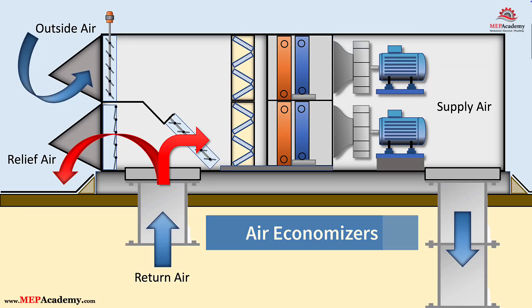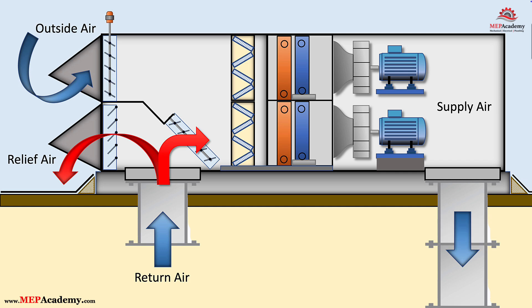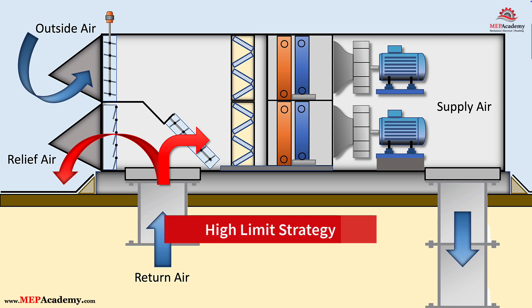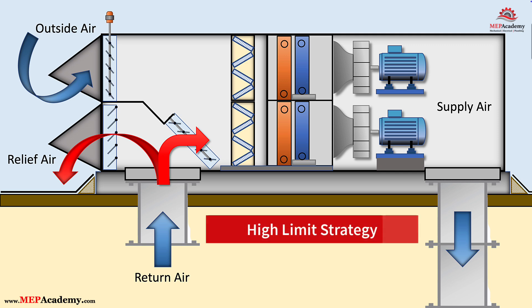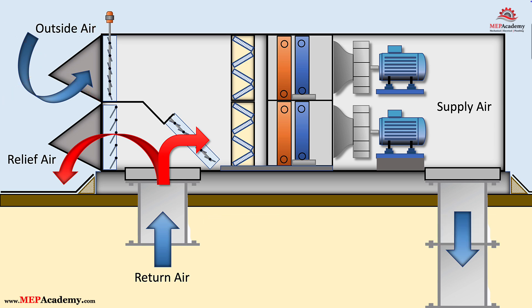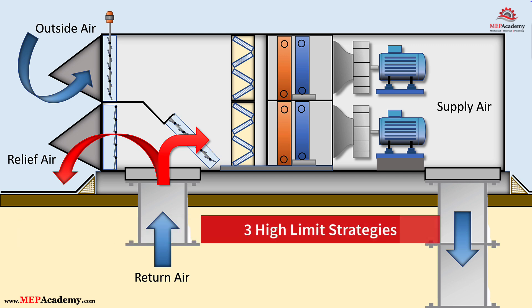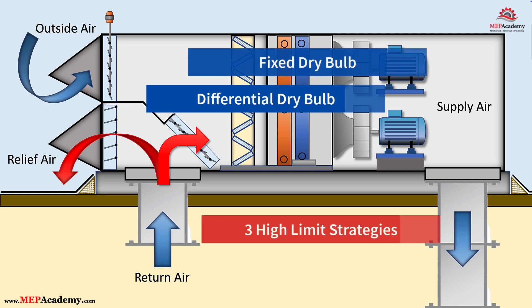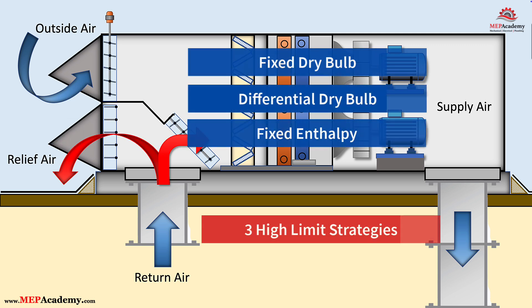Air economizers are a vital component of modern HVAC systems, designed to reduce mechanical cooling loads by using outdoor air for free cooling whenever conditions allow. High-limit strategies determine when outdoor air should not be used, typically to avoid introducing excessively hot or humid air that could increase cooling loads or compromise humidity control. In this video, we'll examine three common air economizer high-limit strategies – fixed dry bulb, differential dry bulb, and fixed enthalpy – with examples of each and the issues they may encounter.